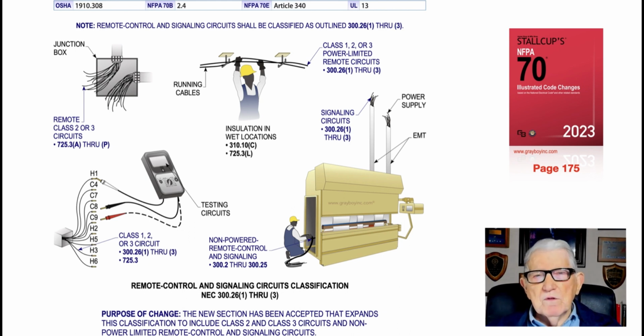Now we have to go to an article that would deal with that, but they're discussed in 300.26, 1 through 3. But let's move over to the square box, and you see all the signaling circuits coming into that junction box. And notice they're Class 2 or 3. We can read up on those in 725.3(A) through (P). And if you want to know the output and get a good feel for that, just go to Tables 11(A) and (B) on page 728. The A tables are for AC, the B tables for DC. And they usually operate at 1,000 volt-amps or less at 30 volts or less.